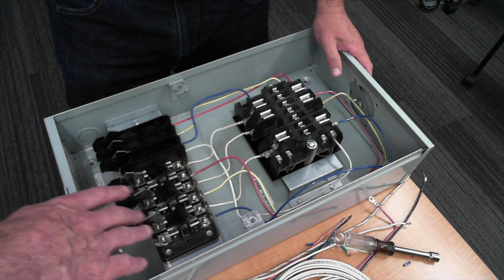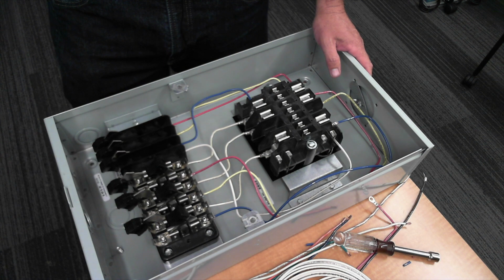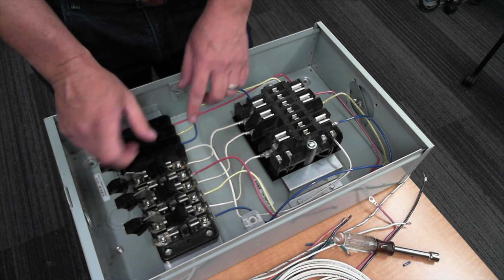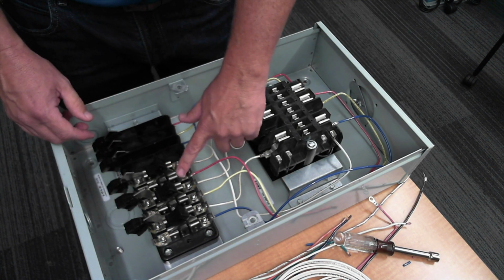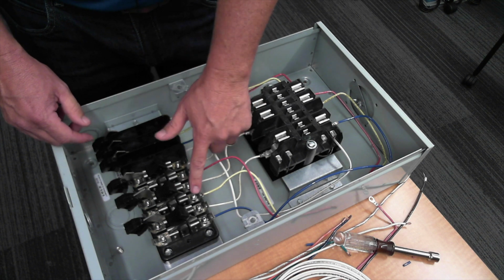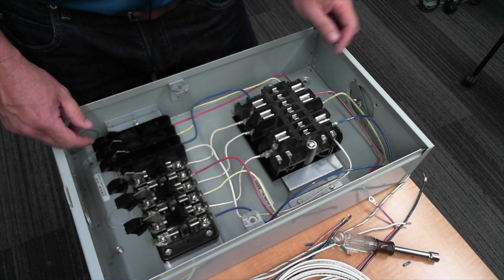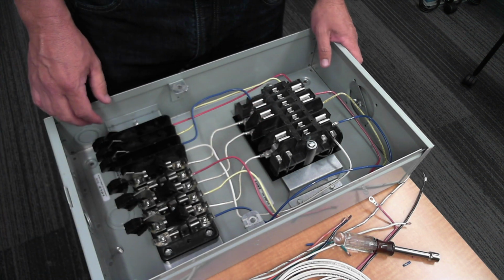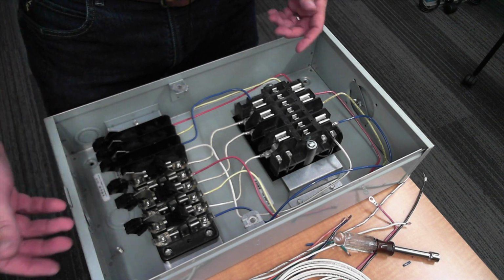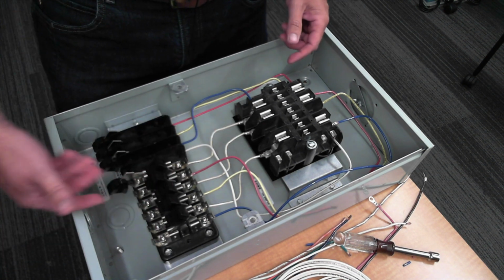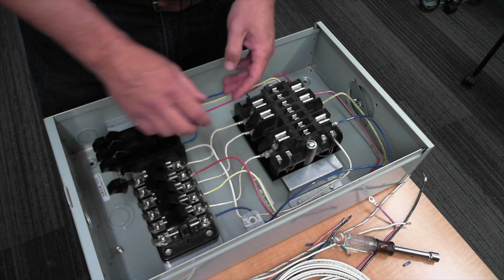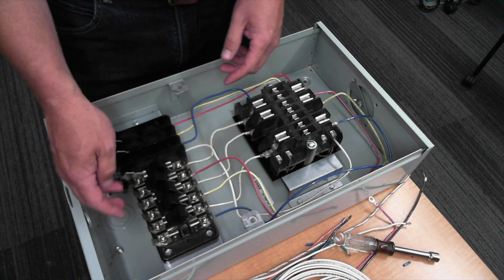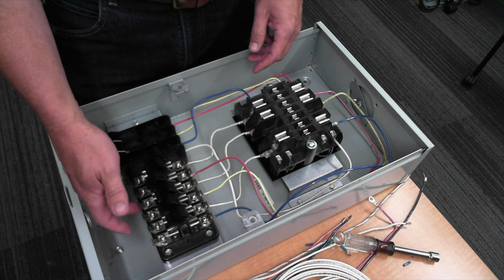So what's your flow of current then over here from the way you got it wired? So return potential would be A, return B, return C. So which way is your current going through these wires? They're actually coming from your transformer this way up to your meter base, then it's going to return right here, and then we're going to loop down here at the bottom, our returns together, and tie them to the can.